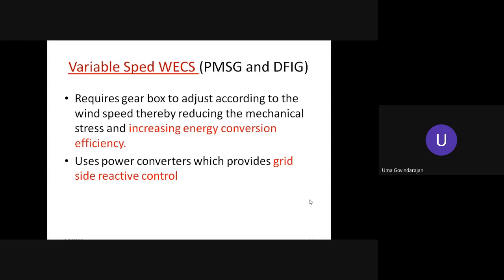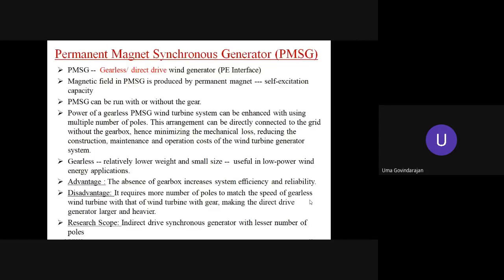It also helps to reduce the mechanical stress and thereby helps to increase the energy conversion efficiency. It uses power converters, which help to provide grid side reactive power control, or to provide reactive power support to the grid. The next one is the permanent magnet synchronous generator. It is a gearless direct drive, which is also one of the advantages, but it processes the entire power via a power converter.